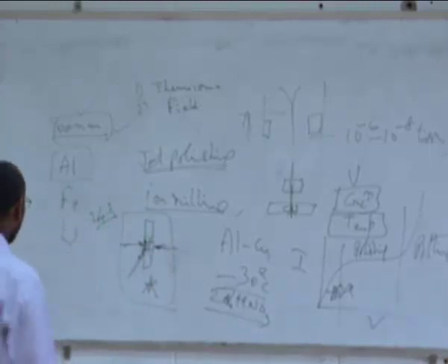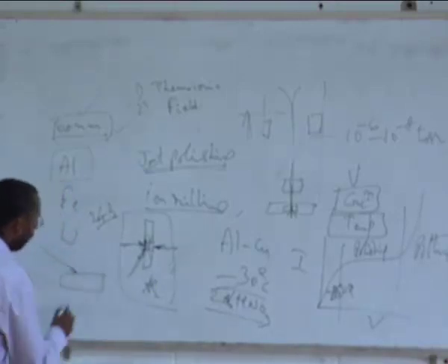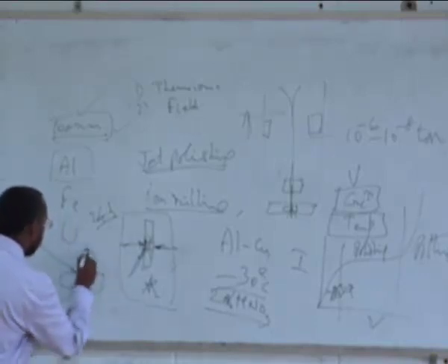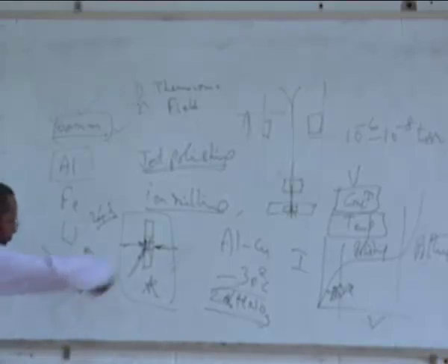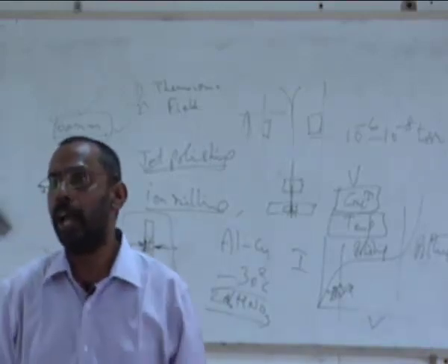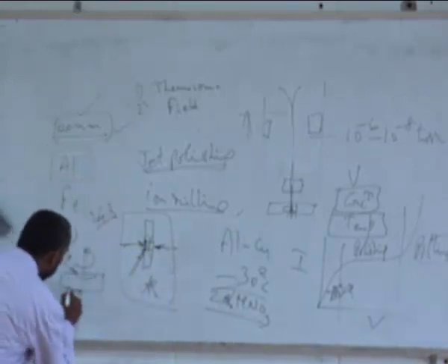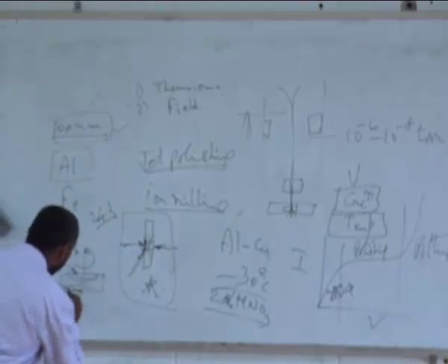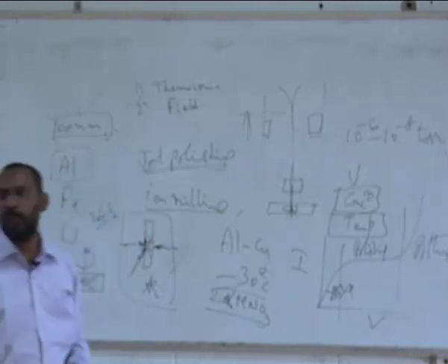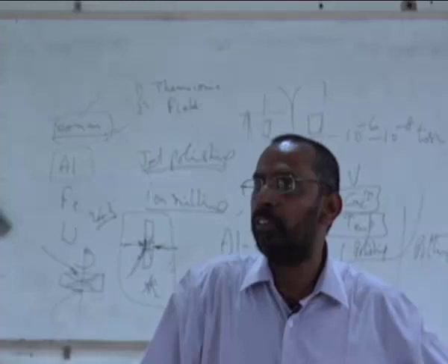You keep the sample horizontal and allow the beam to fall at an angle and keep rotating the sample around this particular axis so that the sample is being dissolved, or sputtered away, atom by atom, and in the process you see the sample starts from both sides becoming like this, and finally at some stage there will be a hole formed. Again a similar principle, that the hole is detected by a photocell and the machine is allowed to stop.